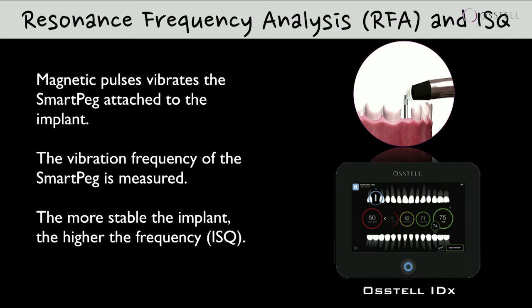How do we actually measure? We attach a smart peg to the implant, and by means of this instrument we send a magnetic pulse, creating a vibration which comes back to the instrument. We measure the frequency and transfer it to an ISQ value. What you see on the right-hand side is the newest generation of the Osstell technique — the Osstell IDx. The more stable the implant, the higher the ISQ value.